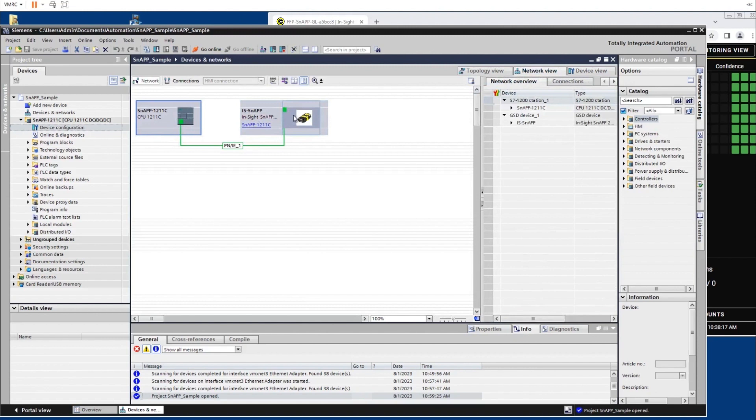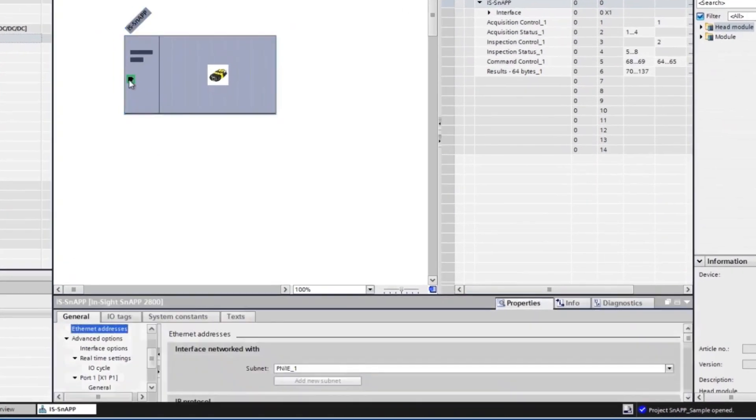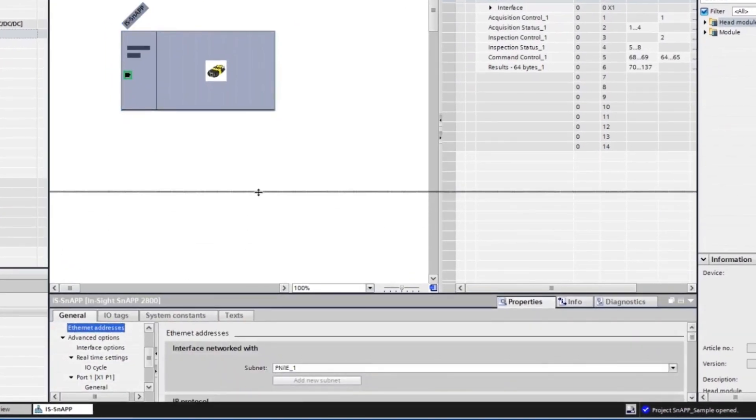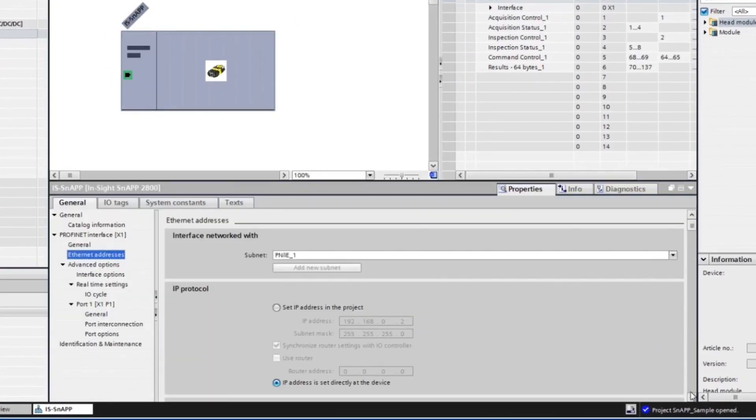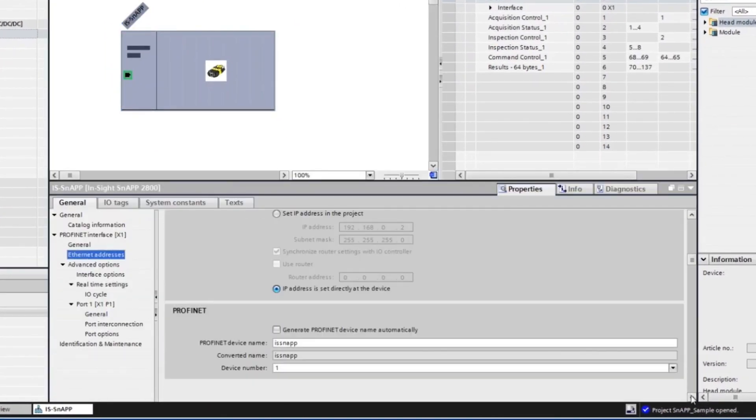When looking at the device on PROFINET, there are settings that need to be set up initially to communicate. The PLC project typically will default to the first option, setting the IP address in the project. Change this to the IP address is set directly on the device option. We do this because we set the station name and IP address earlier in the process.